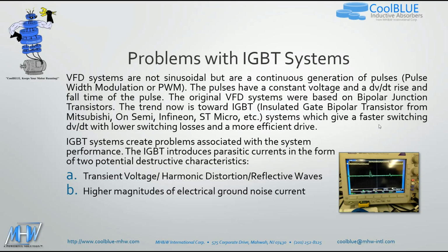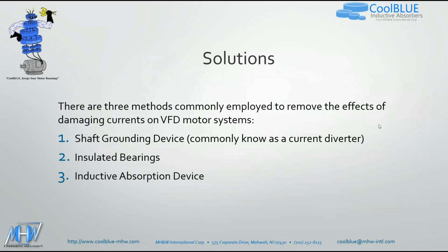These new IGBT drives introduce parasitic currents in the form of two potentially destructive characteristics. A, transient voltage, harmonic distortion, and reflective waves, and B, a higher magnitude of electrical ground noise current, which is what we're going to focus on. There are commonly three solutions to this problem to remove the effects of the damaging currents on VFD motor systems. Number one is a shaft grounding device, commonly known as a current diverter. Number two would be an insulated bearing. And number three would be an inductive absorption device.